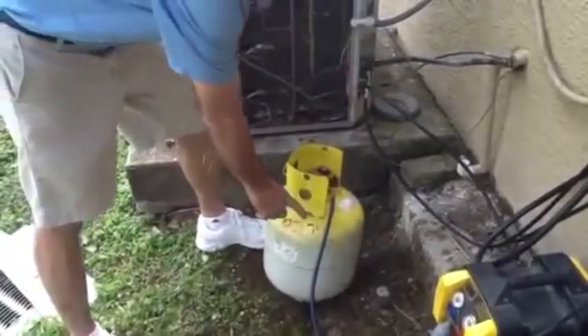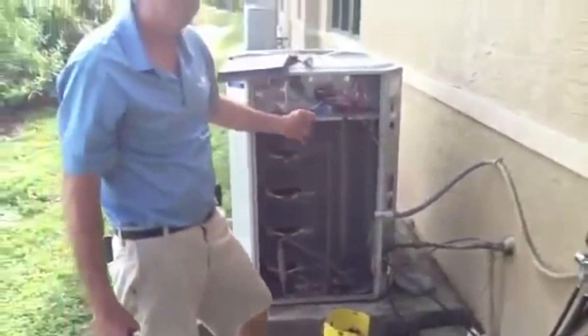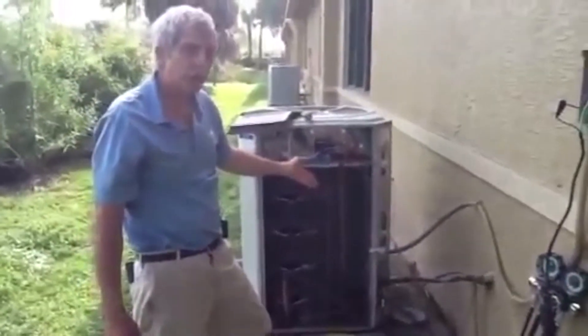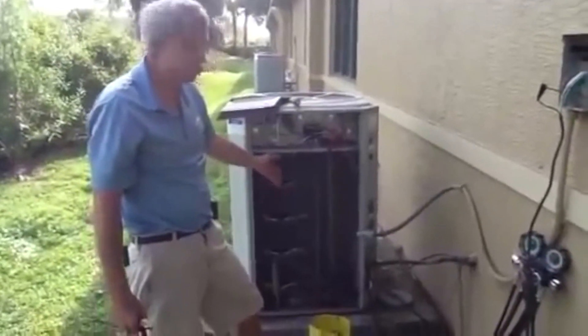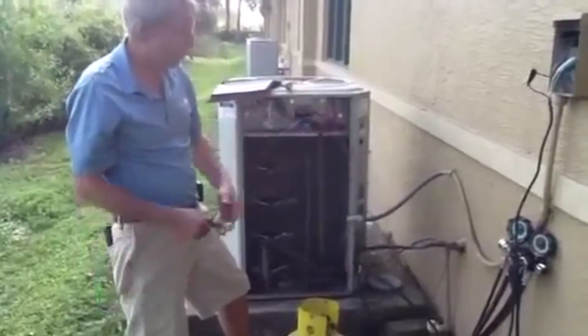This morning we're going to talk about recovery of R-22. These older units, mostly over five years old particularly, are going to be R-22 units. This particular unit is a Trane. The compressor failed this morning, so we're going to recover the freon.